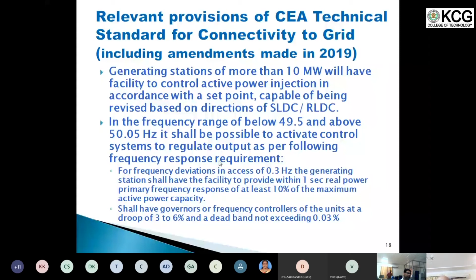One is that these plants can be operated based on a set point in megawatts. That's okay. But earlier, the requirement for frequency control was not there. It has been introduced now. It says that in the frequency range below 49.5 and above 50.05, it shall be possible to activate control systems and regulate output as per the frequency response requirement. That is, for frequency deviations in excess of 0.3 Hz, the generating station shall have the facility to provide, within 1 second, real power primary frequency response of at least 10% of the maximum active power capacity.